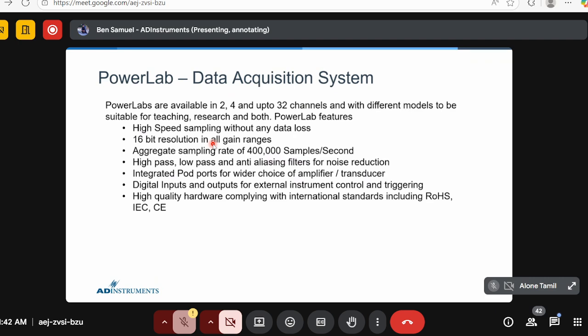Coming to resolution, what is the resolution? Basically, a 16-bit resolution refers to how precisely an analog signal can be represented when converted to digital form. Bits represent the number of binary levels used to encode the signal. 16 bits means 2 to the power of 16, which comes to 65536 discrete digital steps. So these many steps it will take to interpret a signal. It will break your input signal into 2 to the power of 16 slices. By this, it detects very small changes, and even the smallest signal will be visualized with the highest accuracy or better resolution. Then it gives a smooth and detailed digital signal. That is about the resolution.